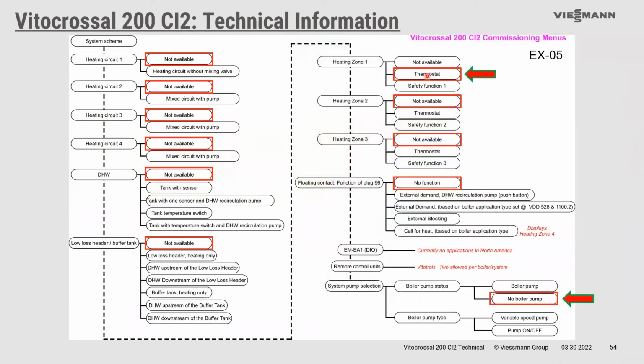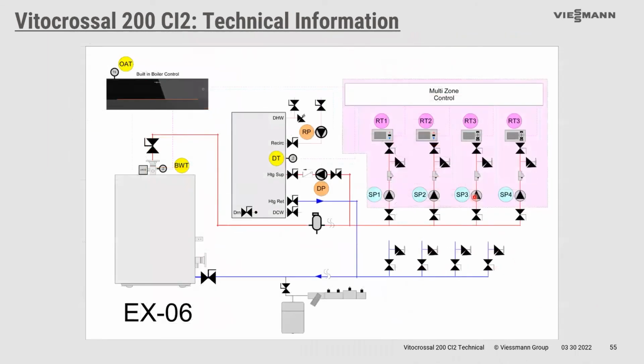And again, we make a zone circuit or heating zone and we say no boiler pump. Now, this is a little different in that the domestic is added to it. So now we have a potential priority issue because there's no domestic priority as far as the flow goes. We're not controlling this pump. The multi-zone control is controlling this pump.